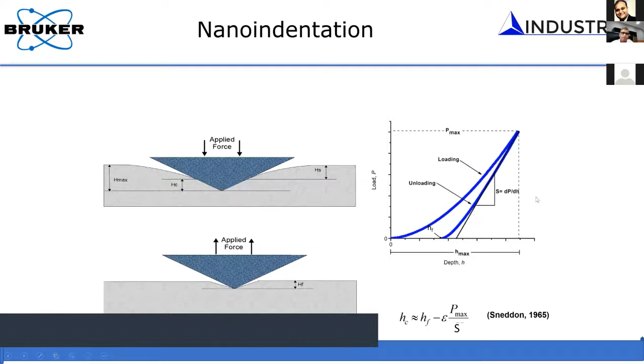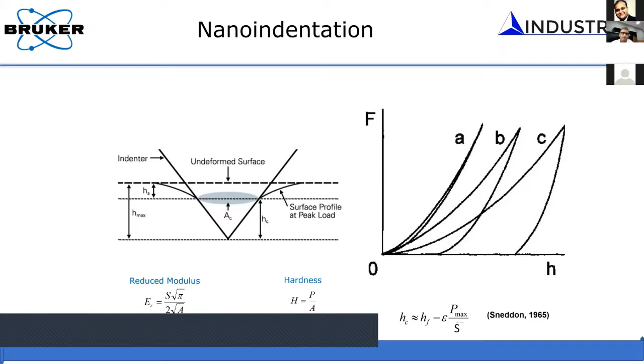By knowing the load you are applying, the stiffness that you measure for a given load, and the depth of indent and all of that. Okay, so if you have this load-displacement curve, then you can do this hardness and modulus measurement. Like I said, it depends upon the material that you're studying. Some materials have more elastic behavior, some will have more elastoplastic behavior. So depending upon the material, it will have a unique fingerprint. And that's how we can use this technique to identify failure in materials, structure-property correlation, and things like that.